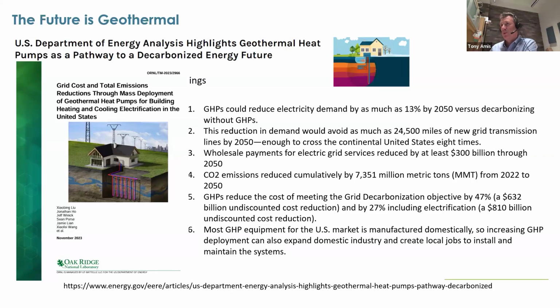Some of the bullet points show that when people talk about putting heat pumps into homes all over the place, they are generally air source heat pumps. The trouble is air source heat pumps are 3 to 4 times less efficient than a ground source heat pump, for the very reason that the ground temperature, as Hursit said in his slides, averages about 55 degrees Fahrenheit even on the coldest day.